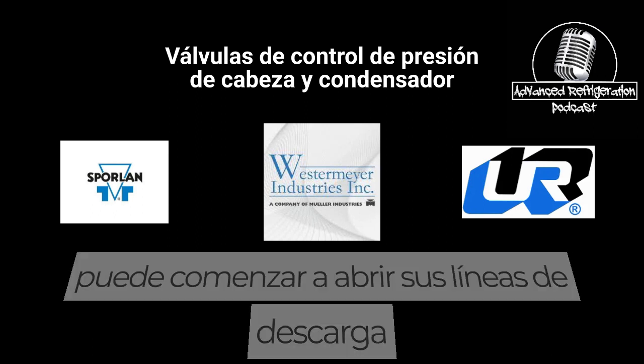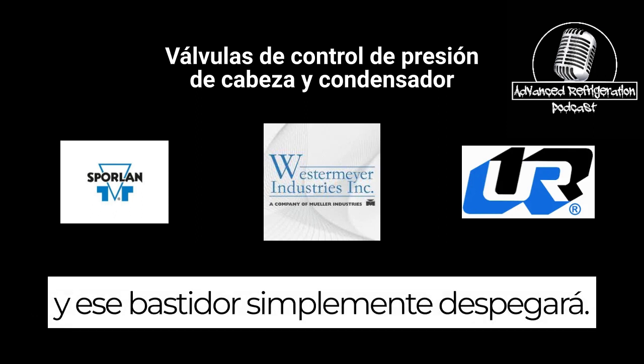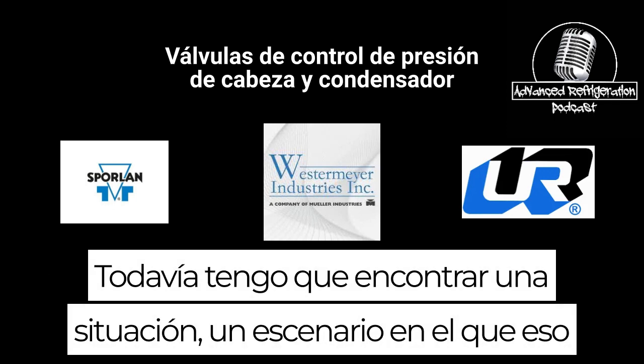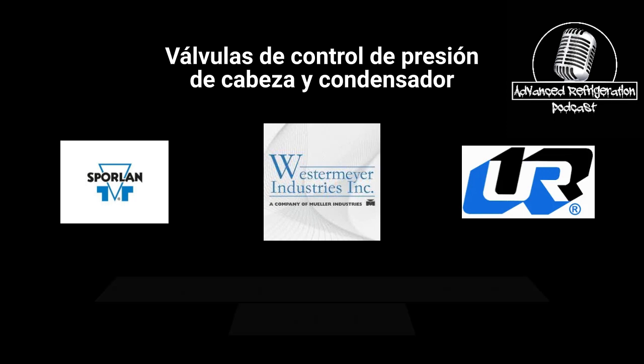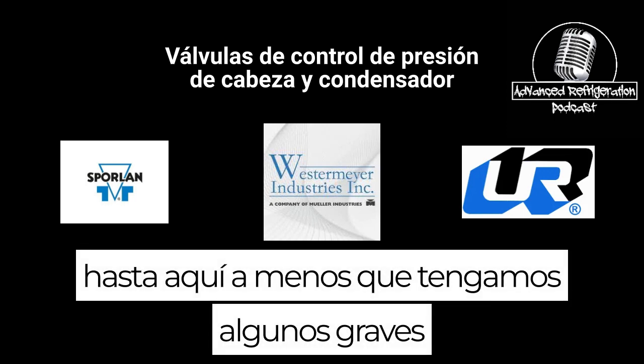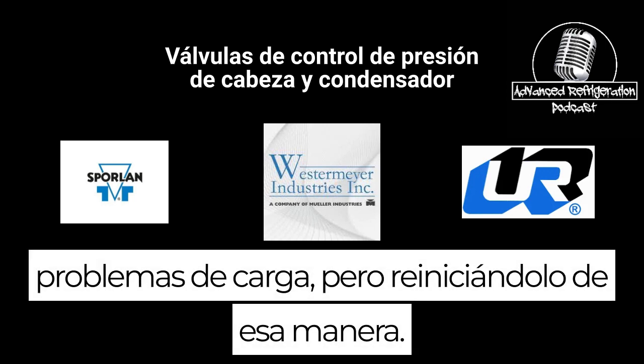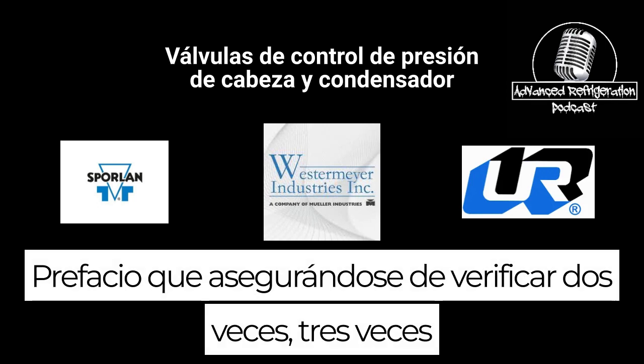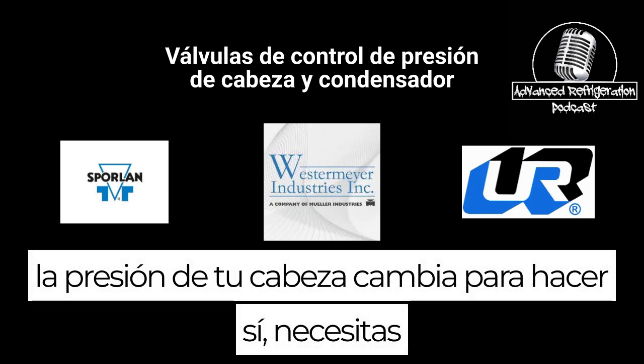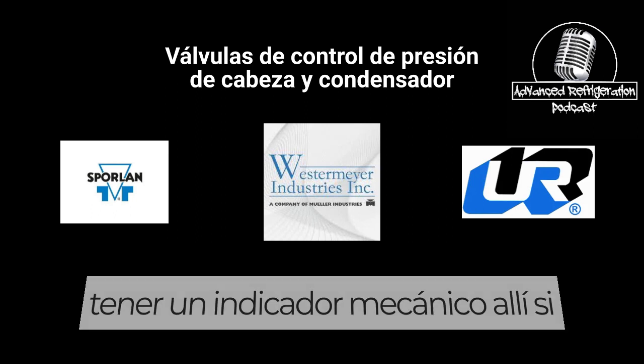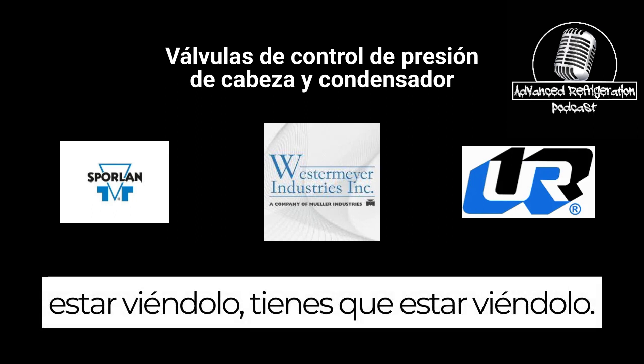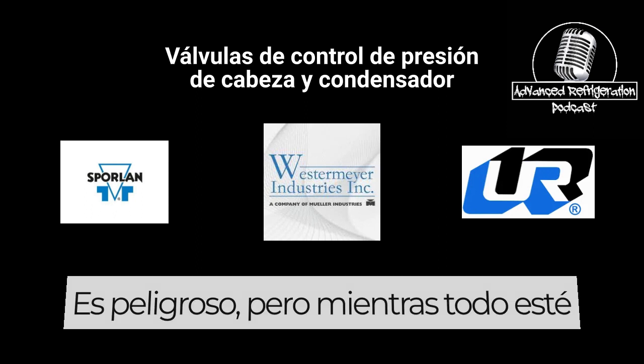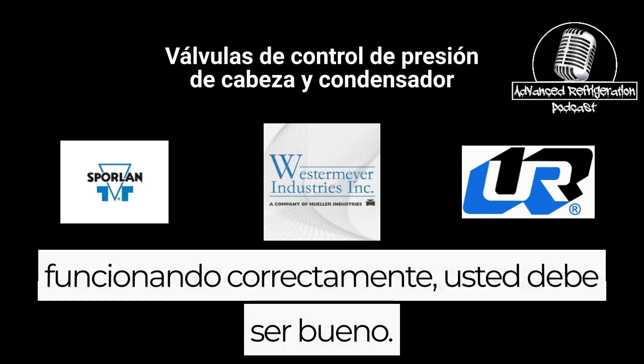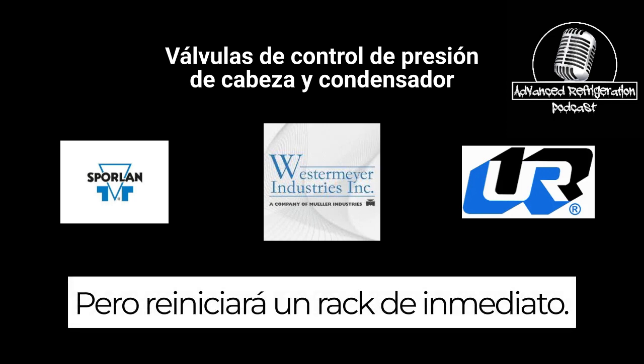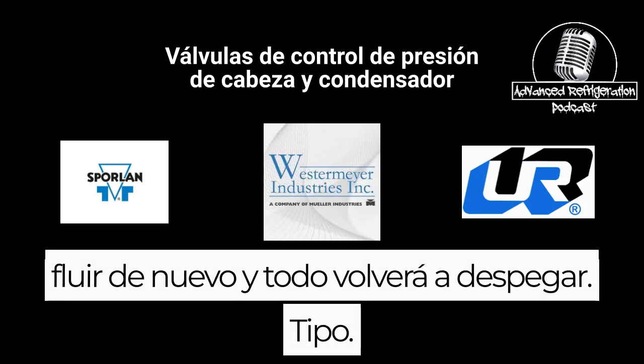It's going to start popping up, and then you can start opening your discharge lines up and that rack will just take off. I've yet to find a scenario where that did not restart that rack within like 10 minutes. Generally we don't ever have to wrap them up here unless we have some severe load issues. But I mean, restarting it that way, preface that by making sure that you double, triple check your head pressure switches. You need to either have a mechanical gauge on there or be watching it. It's dangerous, but as long as everything's working properly, you should be good. It'll restart a rack right away. Within like 10 minutes, all that liquid will start flowing again and everything will take back off.